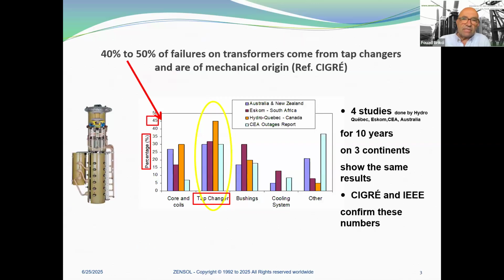So 40 to 50% of failures on transformers come from tap changers and are of mechanical origin. These numbers come from Cigré. So 4 studies done by Hydro-Québec, Eskom, CEA, Australia for 10 years on 3 continents show the same results. And Cigré and IEEE confirmed these numbers. For example, here we have 45% in orange. These are the numbers from Hydro-Québec.